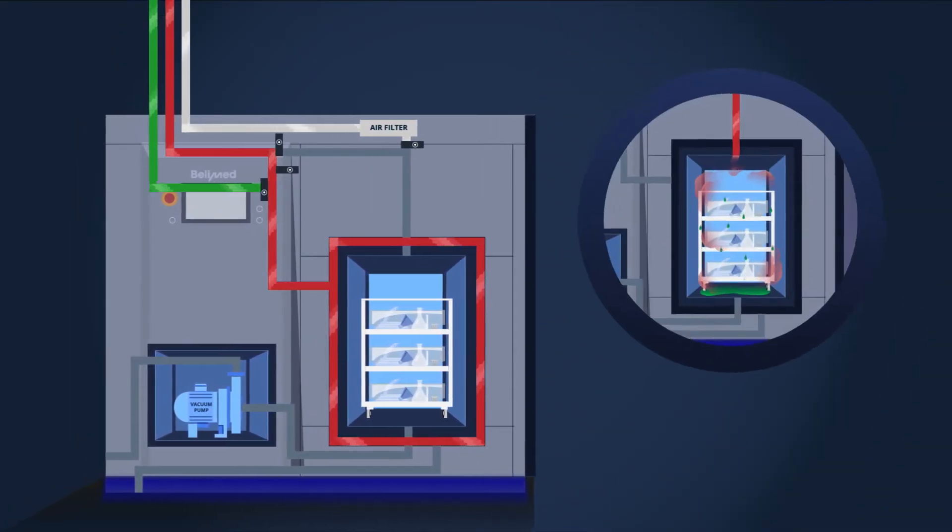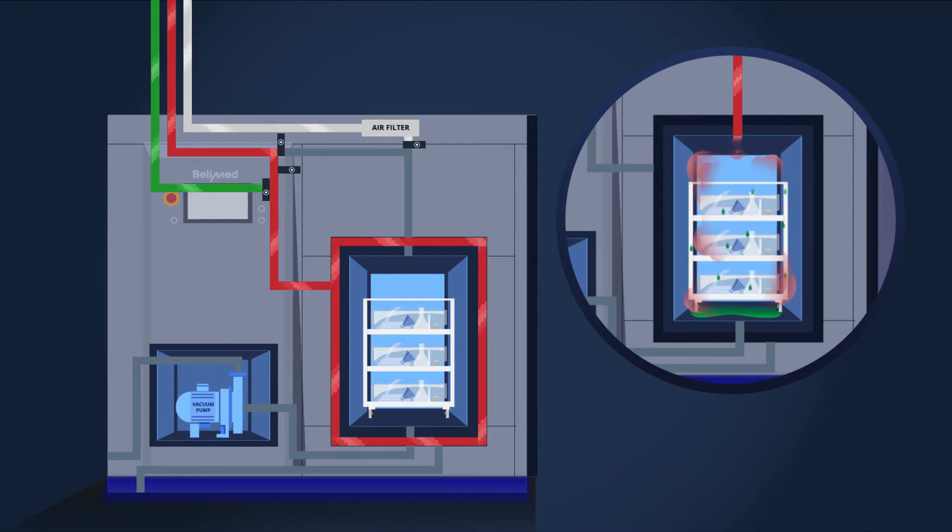If the walls are not heated first, the steam needed later inside the chamber for sterilization would condense and cause the products to be sterilized to become wet.